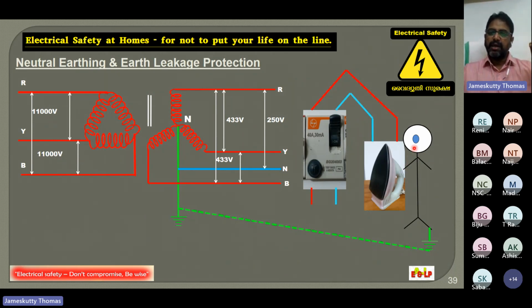See here, actually this person can withstand only up to 30 milliampere current, because in a human body, the heart is the most sensitive part. We will study it later. So here we should get the protection for 30 milliampere, or I can say this RCCB is rated for 30 milliampere. When there is a difference of 30 milliampere current between this phase and neutral, the RCCB will get tripped and the person will be safe. Here you please note that the fault current passing through the person is returning to the source. See here, it is returning to the source or the transformer through earth to the earth neutral.